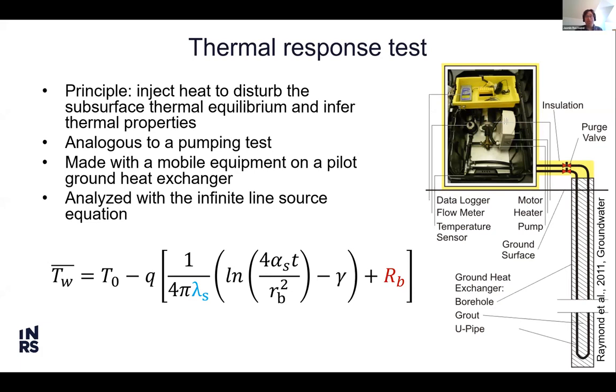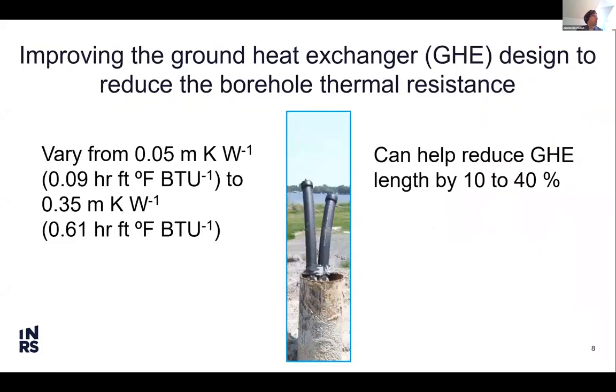So by monitoring the temperature in the thermal response test, I can obtain two things: the ground thermal conductivity and the borehole thermal resistance. But often those two parameters are connected and dependent on each other. So we have to find ways, right? There could be more than one solution of thermal conductivity and borehole thermal resistance that will fit the thermal response. So we have to find ways to distinguish the effect of both parameters.